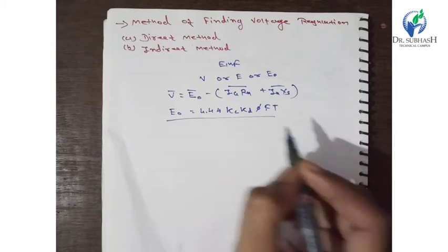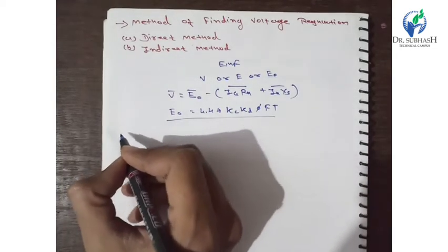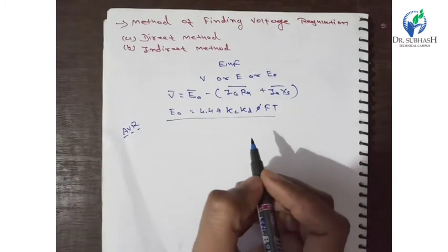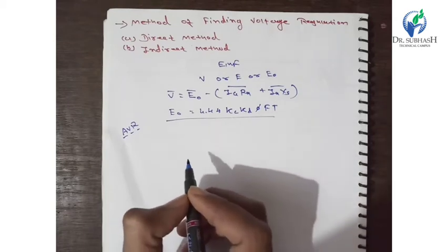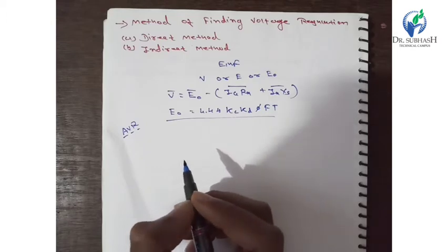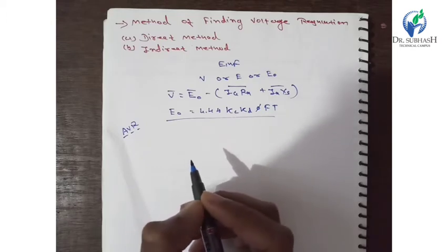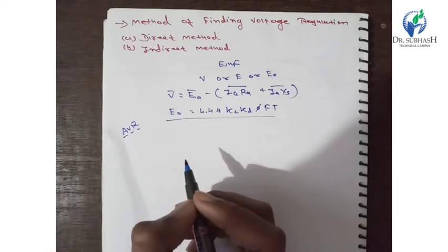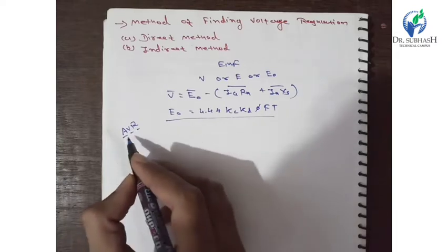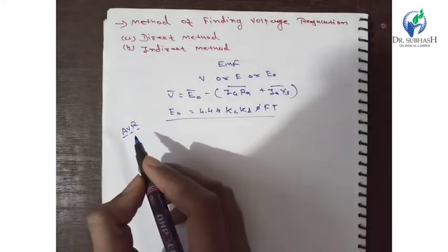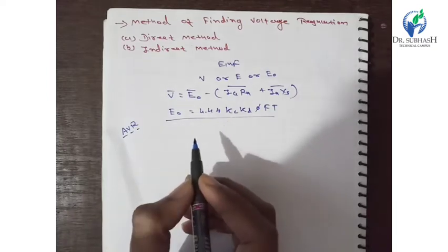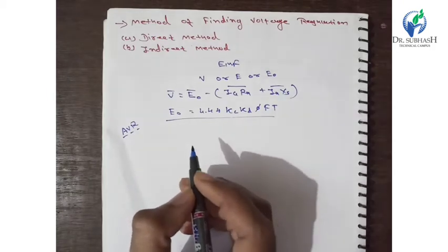The automatic voltage regulator is generally represented as AVR. This system continuously monitors the terminal voltage by taking feedback and then regulates the field current such that the terminal voltage is maintained constant. To design an AVR, we should know the band over which the terminal voltage is regulated and varies under different load conditions.